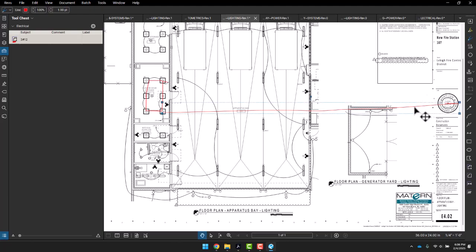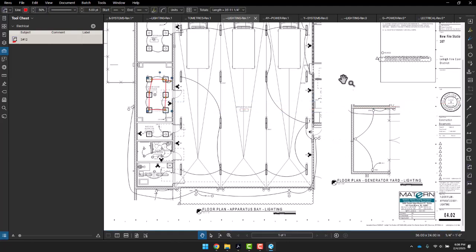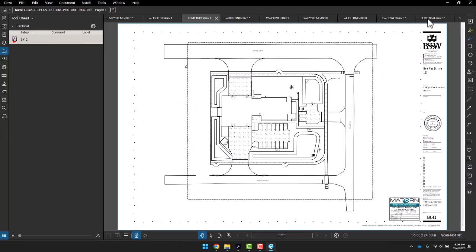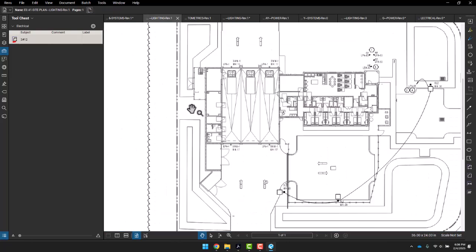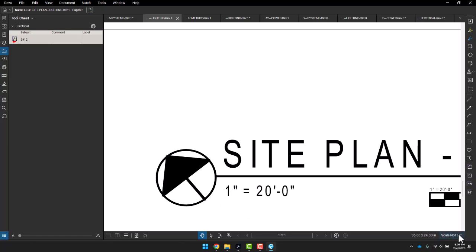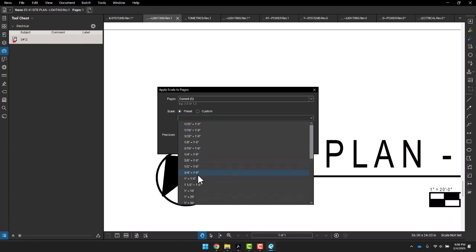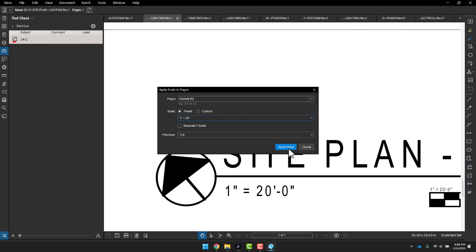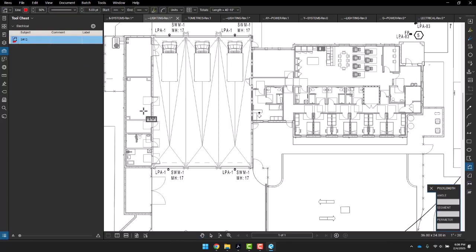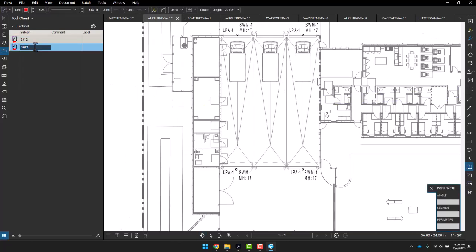So how can you do that? What you need to do is go back to the big drawing over here, and then we do the tag off directly over here. So I'm gonna click the scale over here, 1 inch to 20 feet. Apply scale, and then we know that there is a home run all the way from here to here. Oh, that one is very far, almost 150 feet. So instead of number 12, I'm gonna use number 10 over here. I'm gonna duplicate that and use this one in number 10.